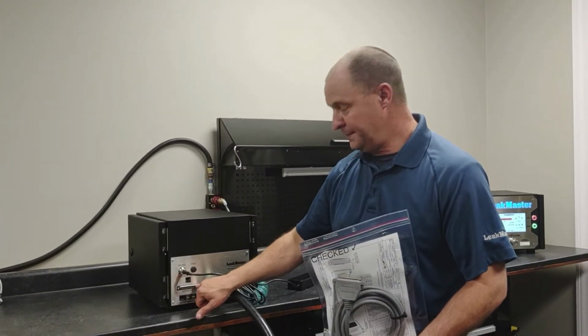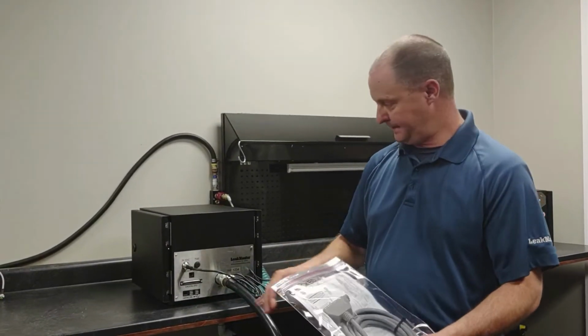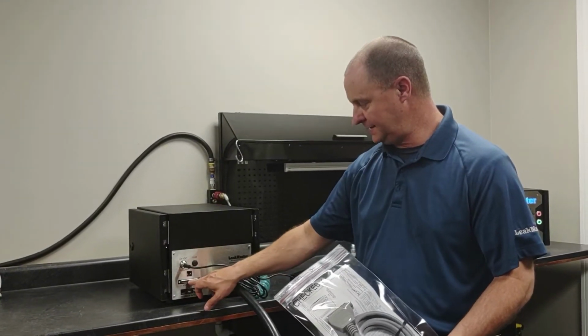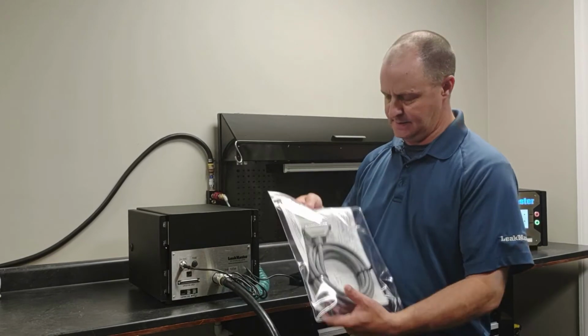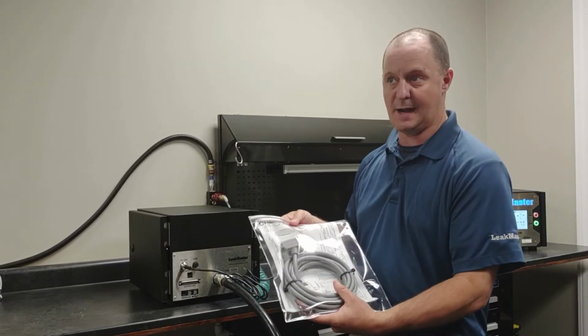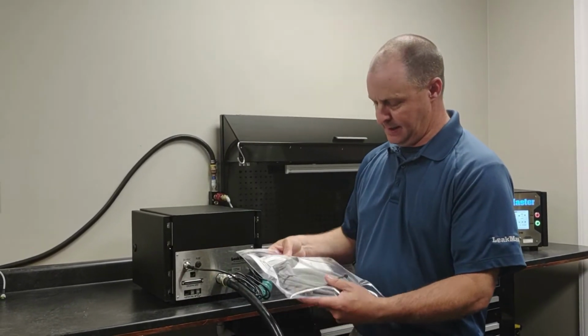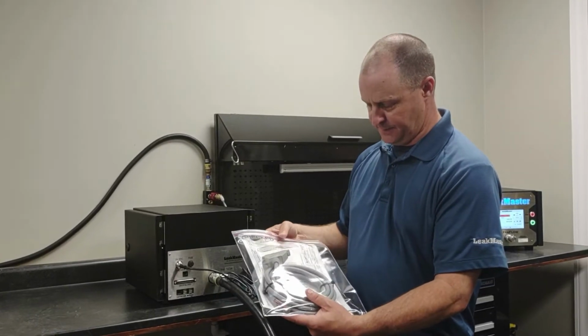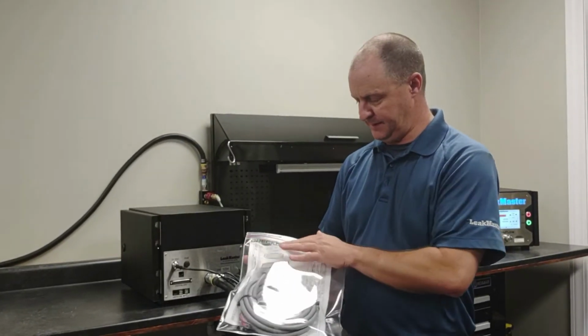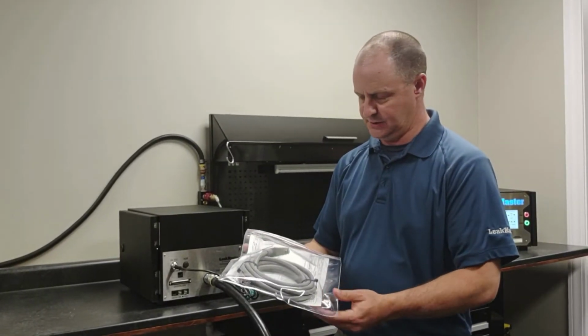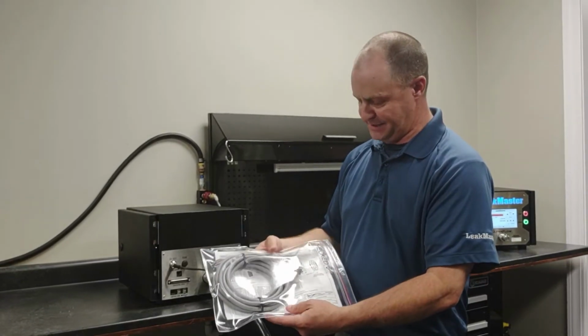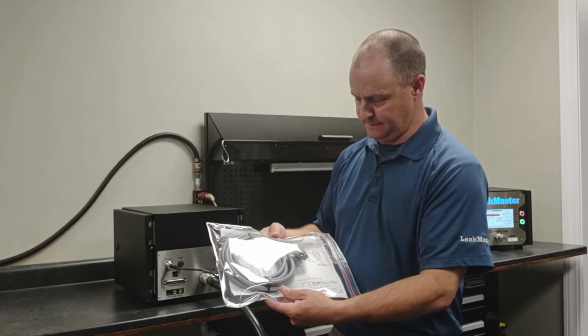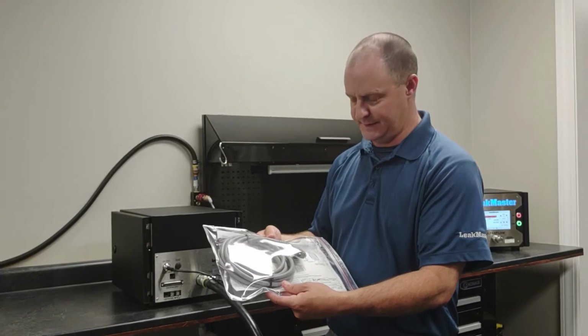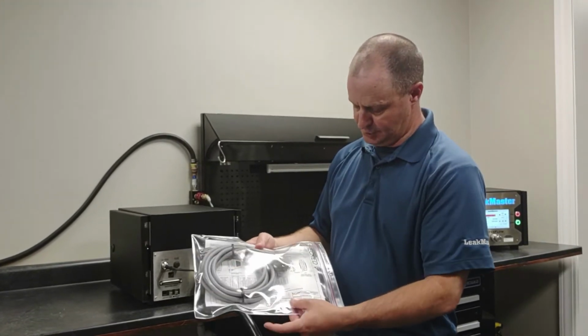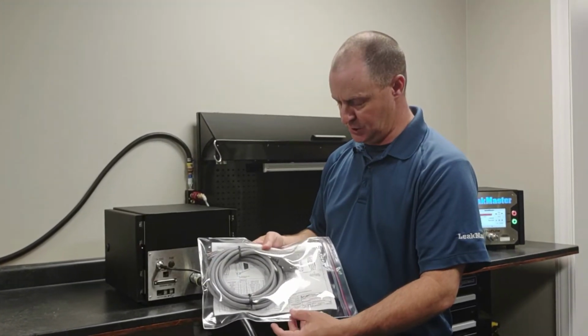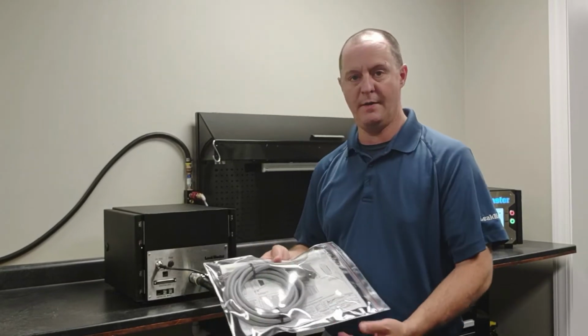If you wanted to communicate via discrete I/O, these are 24 volt inputs and outputs, 16 in and 16 out, and this is the cable option that you would purchase for that. So this is a DB37 cable, and we've already pre-checked this out to ensure that the color code matches the pins on pin 1 through 37, and then there's a drawing that comes with it that shows you all of the color codes so you can wire it up accordingly.